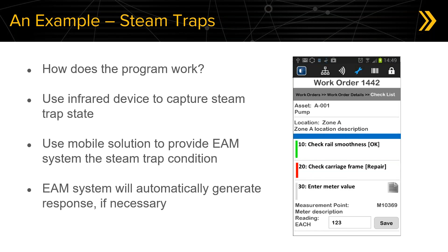Looking at this from a flowchart example, we have a route that generates once per quarter. A technician goes out and performs the route. For each steam trap on the route, the condition is recorded: either it passes, it fails in the blowing state, or it's failed and not blowing at all. Once all that is recorded, the route is completed and the technician's job is finished.